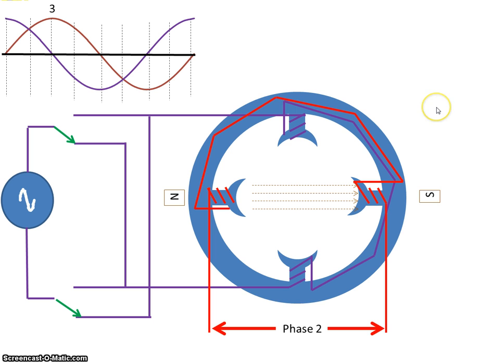So basically, the north pole has moved from there to there to there, and that's in a clockwise direction. So, we can see by reversing the direction of one of the phases, we can change the direction of rotation of the rotor.